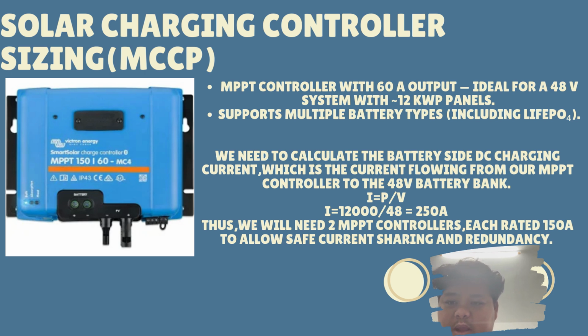First we need to calculate the battery side DC charging current, which is the current flowing from our MPPT controller to the 48 volt battery bank. The formula is simply I equals P over V. The P is 12 kWp and the V is 48 volts, which gives 250 amperes. So we will need two MPPT controllers, each rated 150 amperes. This allows safe current sharing and redundancy.